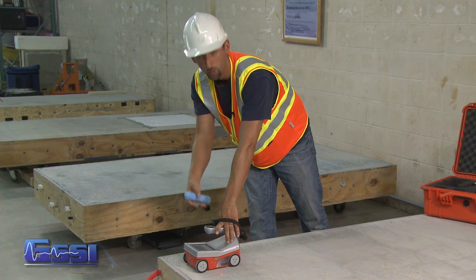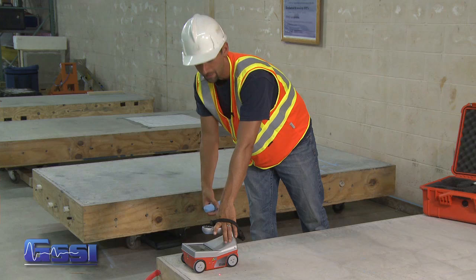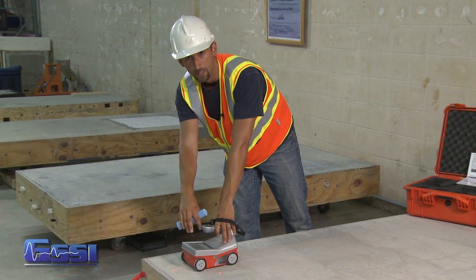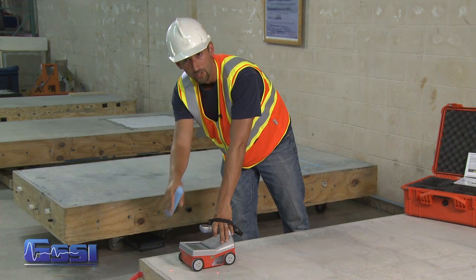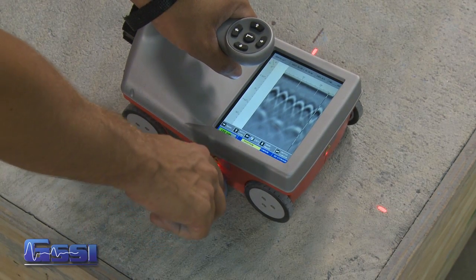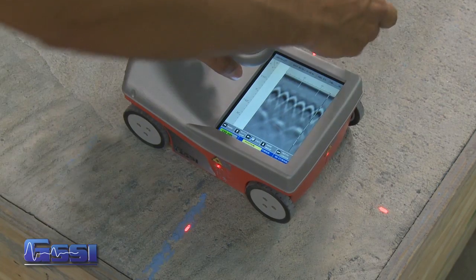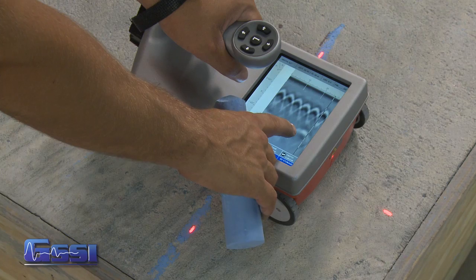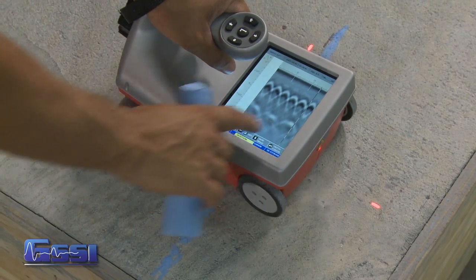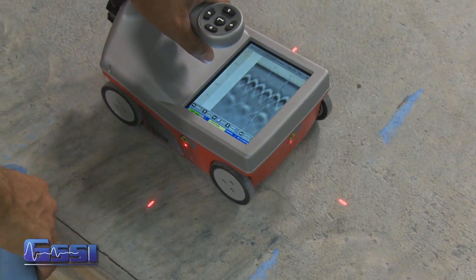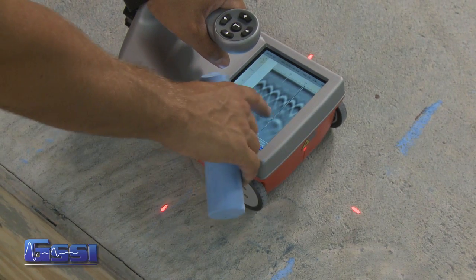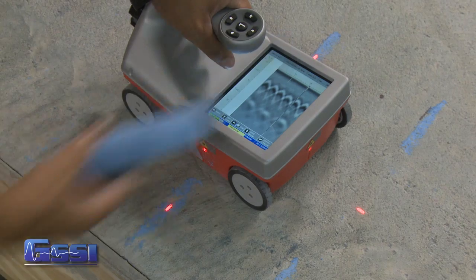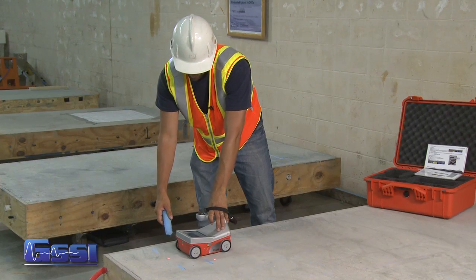We're going to back up and mark out the edges of the apex of the pan decking so we know where we can drill and avoid the valleys where conduits may be. Using the backup cursor, we'll find the edge of the pan decking — one of the flat edges before it tails off — and use our lasers here for marking. Then we back up to the next edge of the apex where it curves down into the valley.